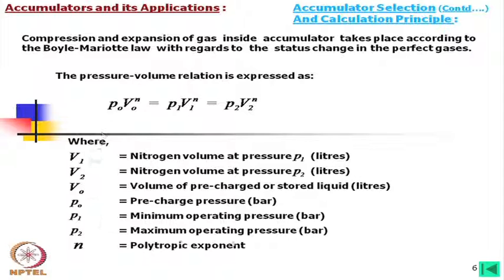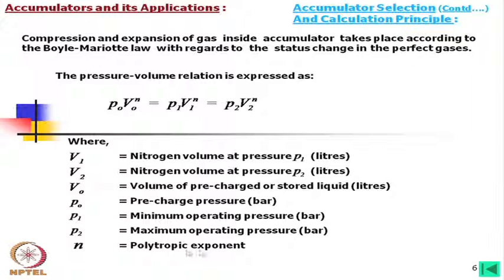To clarify: V1 is the nitrogen volume at minimum system pressure P1; V2 is the nitrogen volume at maximum system pressure P2; V0 is the volume at pre-charge pressure P0. P1 is the minimum operating pressure, P2 is the maximum operating pressure, and N is the polytropic exponent.